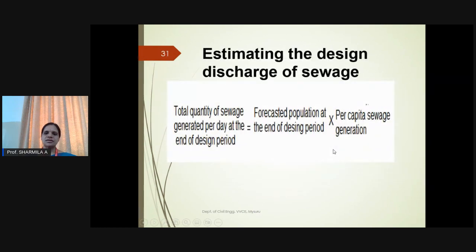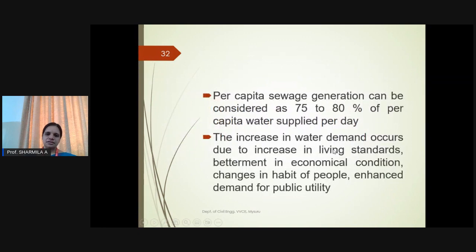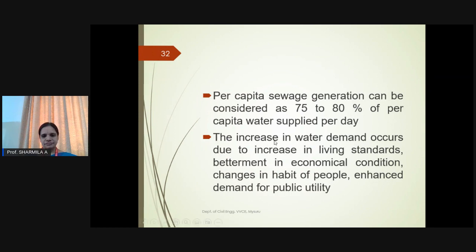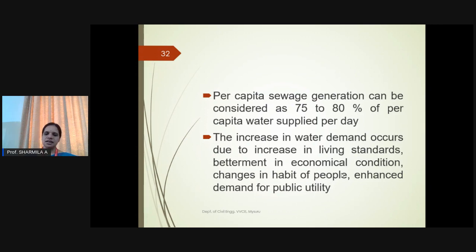For per capita sewage generation, the LPCD (litres per capita per day) water supply value is considered. Approximately 75 to 80 percent of the per capita water demand is taken as sewage generation, i.e., LPCD multiplied by 75–80%. Increase in water demand usually occurs due to increase in living standards, betterment in economic conditions, changes in habits of the people, and enhanced demand for public utilities. In India, an average of 135 LPCD of water is considered.